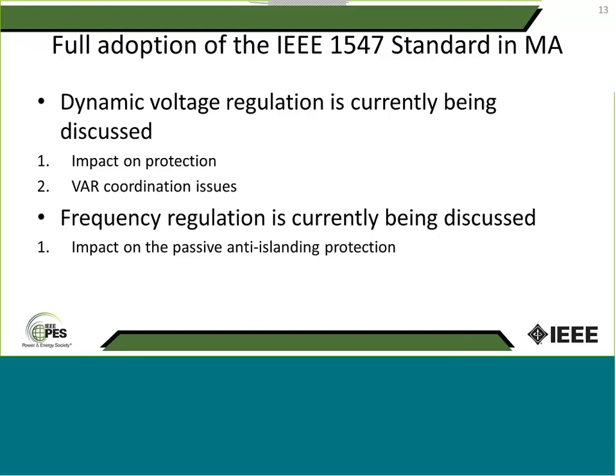So the concept of DERMS and advanced DMS is where I'm going with this: you need to have that sort of automated process in place so that these smart technologies monitor the status of the generators and then send the right setting commands to the generators to adjust the settings based on the existing condition. And in 1547, we mandated the interoperability requirements and the communication requirements. So all new DERs, regardless of size and type, will have the communication capability. That's what we really need for voltage regulation and some other grid support functionalities. Because of that, we're still in the process of adopting voltage regulation. We have some more discussions to go, but we're hoping that soon those will be adopted in the state. And last but not least, the frequency regulation. Right now, we're using the frequency regulation for passive anti-islanding protection.